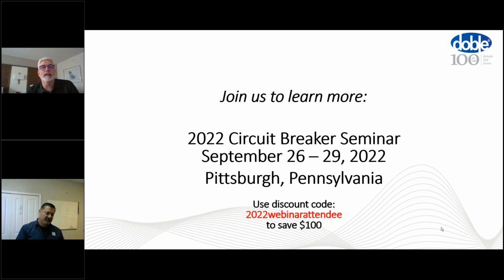From Nick again, great presentation, Billy. Thank you. Expand more on the SF6 self-healing process after an arc is quenched. How long does recombination of SF6 typically take? Would you expect to see values of sulfur dioxide, parts per million byproducts from a high current fault?